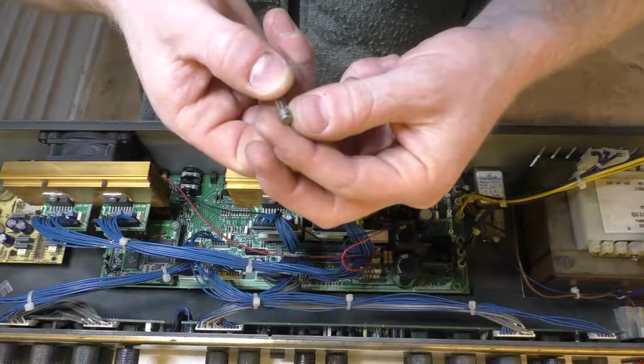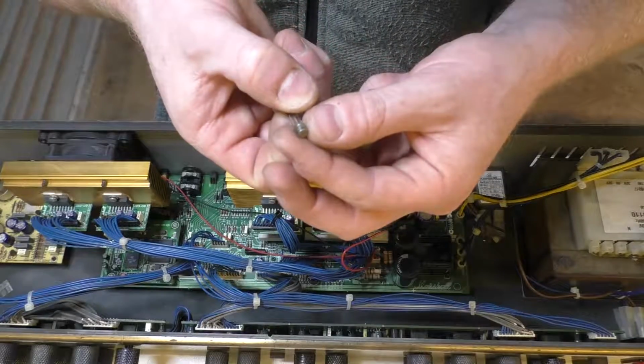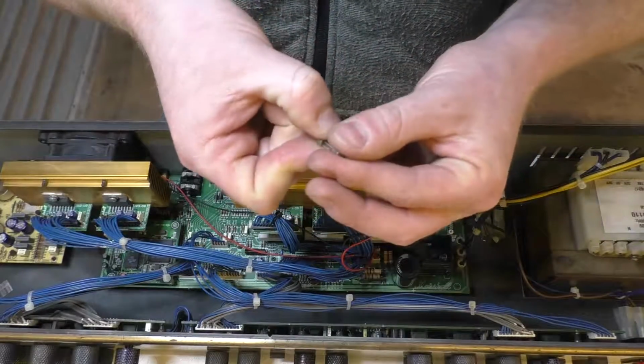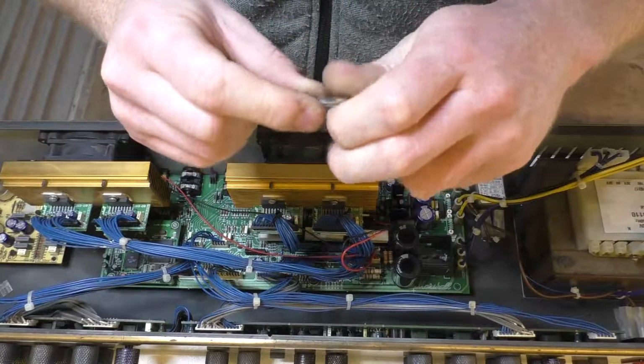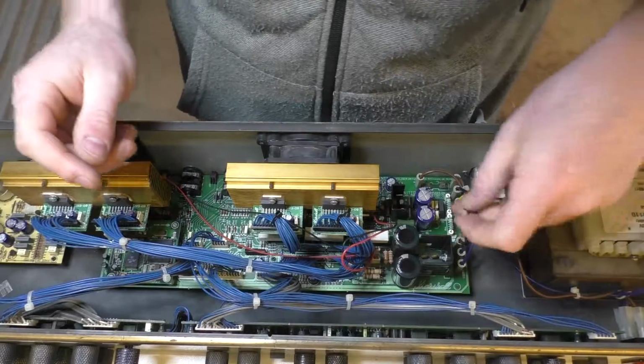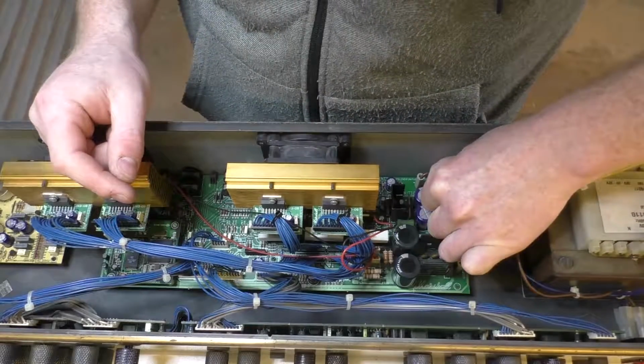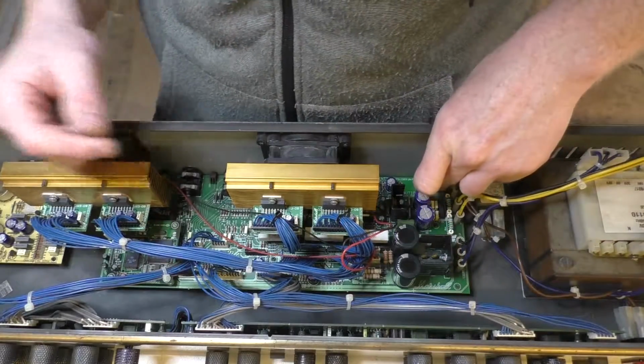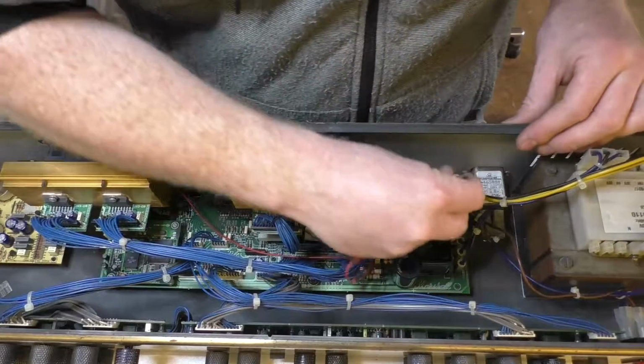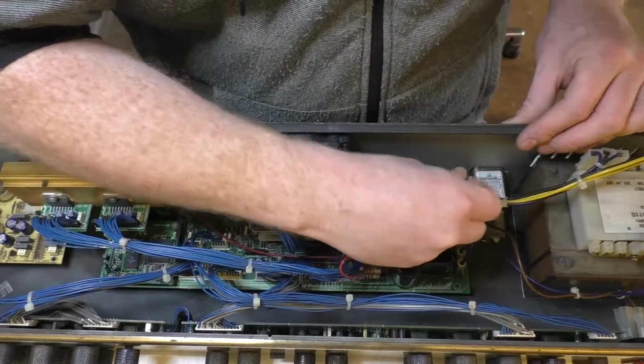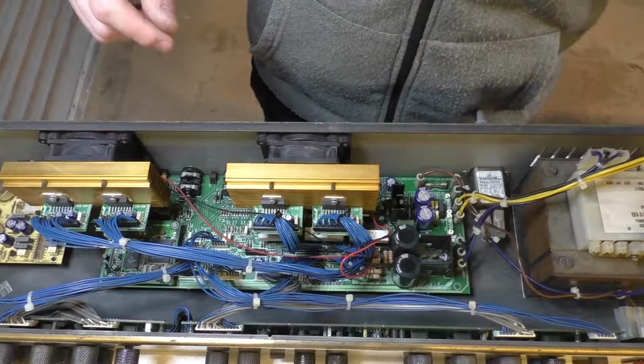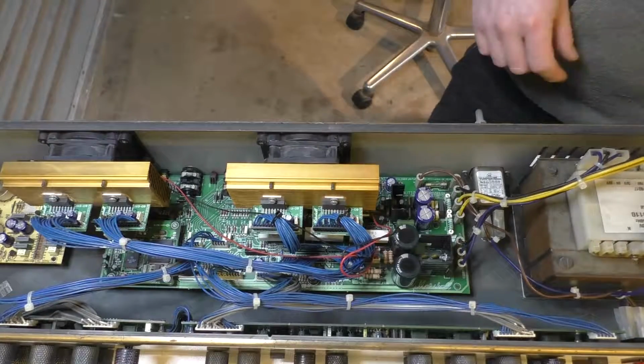Bit corroded, T4E 250 volt, so that fuse is correctly rated. But that fuse is after the secondary. Is it? No, it's before this, it's on the primary. So if it was drawing excessive current, that should be blowing.